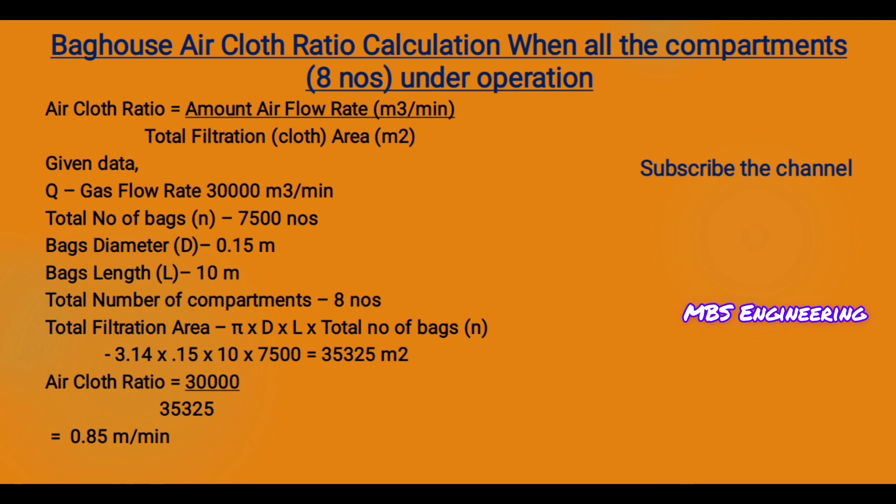The total filtration area equals pi multiplied by D multiplied by L multiplied by the total number of bags. Based on the above data and equation, the total filtration area is 35,325 square meters. The air-to-cloth ratio equals the airflow rate divided by the total filtration or cloth area. Based on the above data and equation, the air-to-cloth ratio is 0.85 meters per minute.